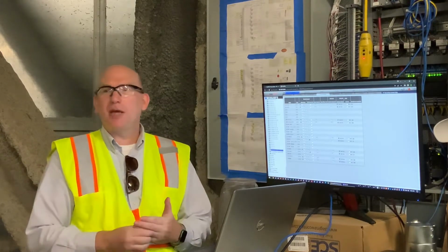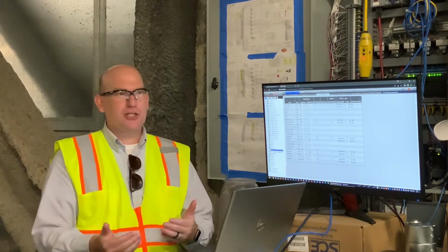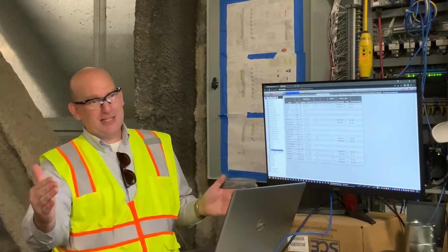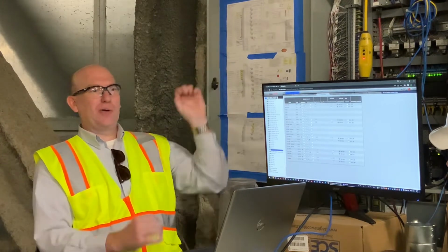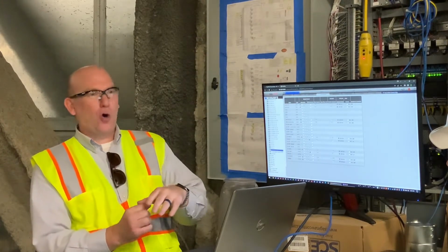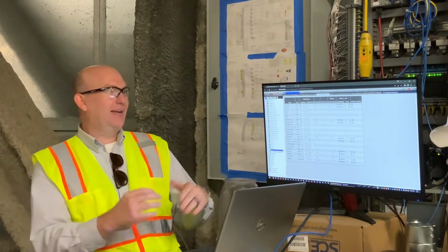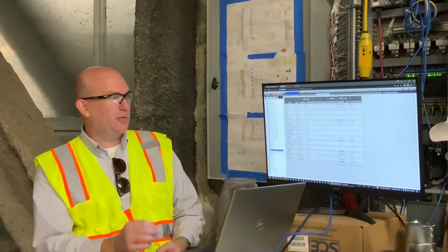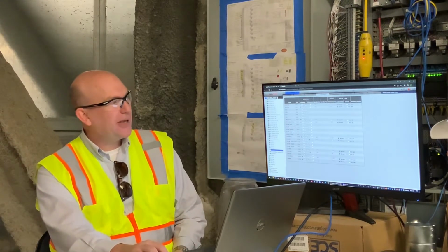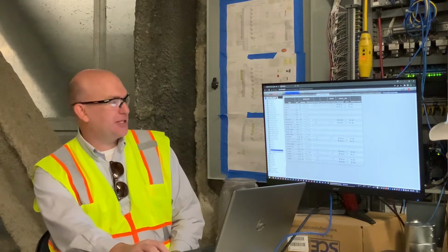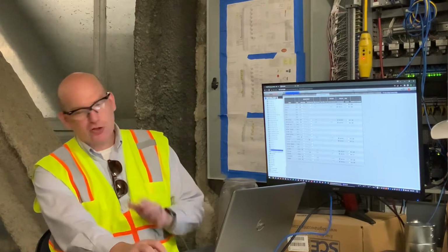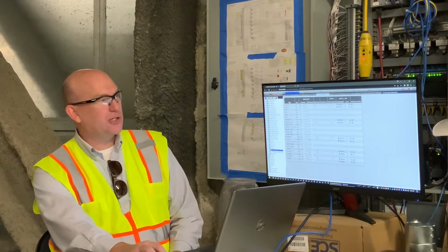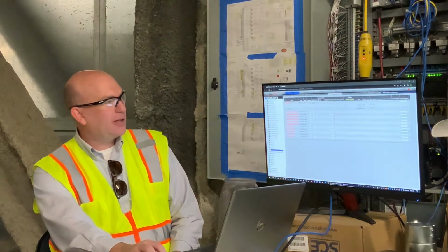A little more common maybe if we're talking about temperature control, discharge temperature control. All of a sudden you have a valve that might be hunting, but if you're only seeing this every 5 minutes, it hunts, goes all the way open, slugs a whole bunch of cold or hot air, and then closes off again, and now you take another sample and the valve's back at a position it normally would be in, right? So this is a place where you can come and make those changes for the sake of troubleshooting. And we'll talk a little bit more about that when we get to the main trending, when we talk more about trending.